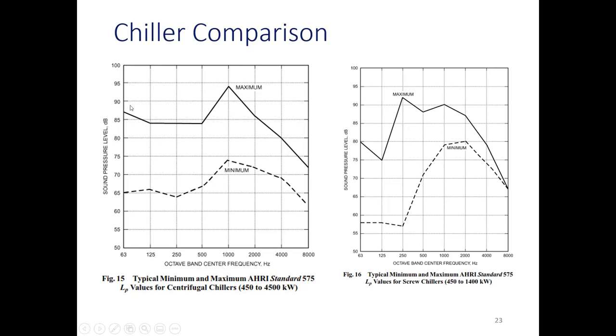And then this lower frequency stuff here is quite a bit louder. Here we have 7 decibels louder, and here again, 7 decibels. That high frequency stuff, even though, like we said, we're more sensitive out here, is usually pretty easy to attenuate if you get some space between you and it. But this is the stuff that's harder to deal with. Say you put up a wall, it's going to diffract over the wall. If it's in another room, it goes through the wall. The transmission loss is not very good at low frequency, so it just goes through. So centrifugal chillers can be pretty troublesome.